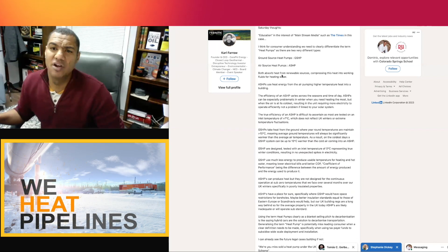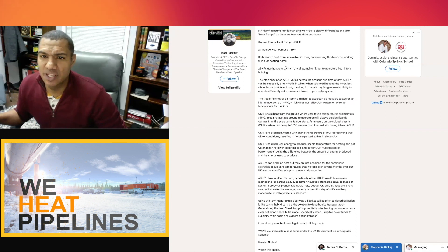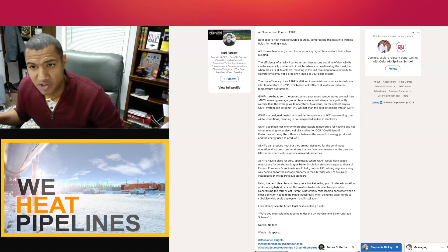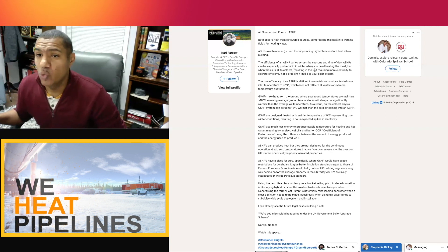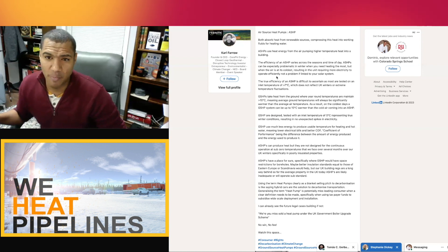Farrow continues: 'Both absorb heat from renewable sources, compressing this heat into working fluids for heating water. Air source heat pumps use heat energy from the air, pumping higher temperature heat into a building. The efficiency of an air source heat pump varies across the seasons and time of day.